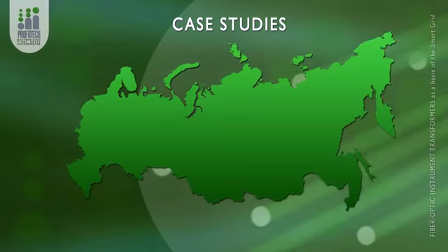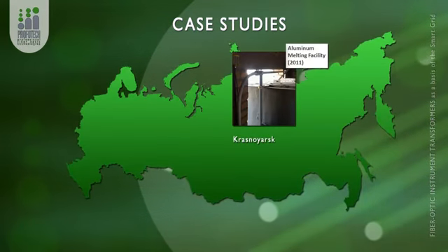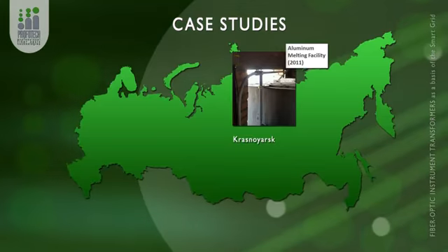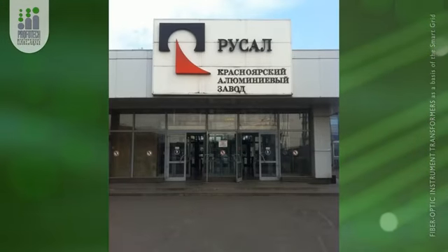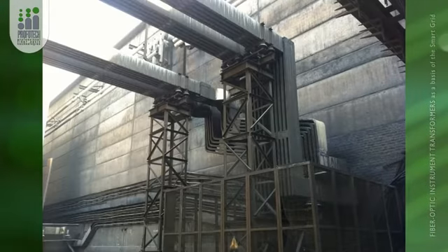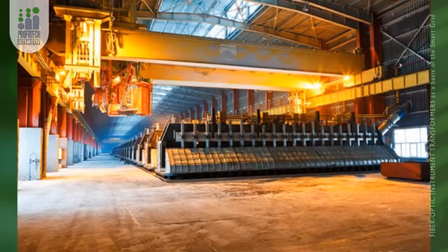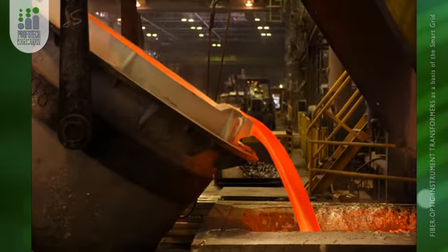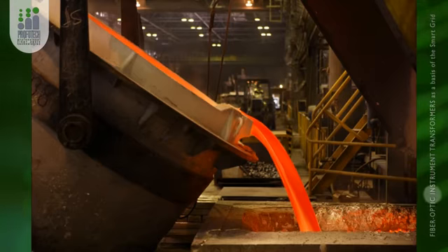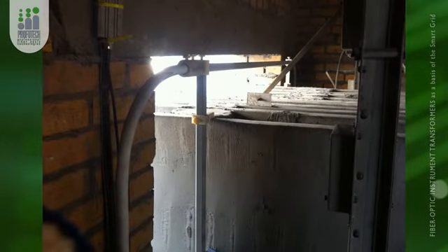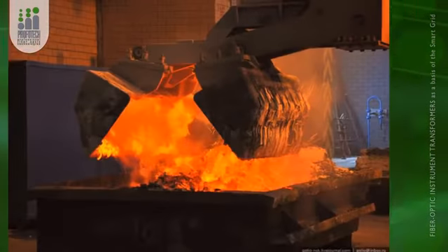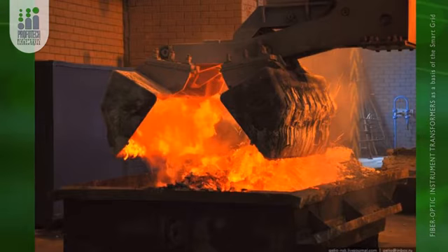Point 5 is the reference application of instrument transformers by Profotech. The first application is an aluminium melting facility in Rusal, Krasnoyarsk, Russia. In 2011, Profotech installed a set of instrument transformers for DC current measurements. This is a very special installation case because this DC current measurement has up to 200,000 amps of DC current. At this installation site we had 5 sensors installed and they are being used for current control at the electrolysis tank series facility.